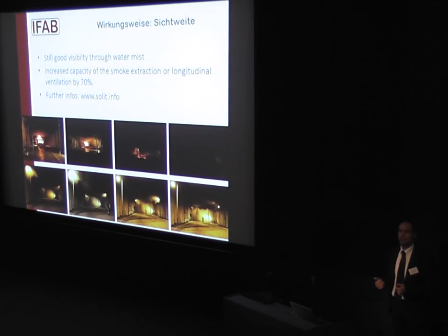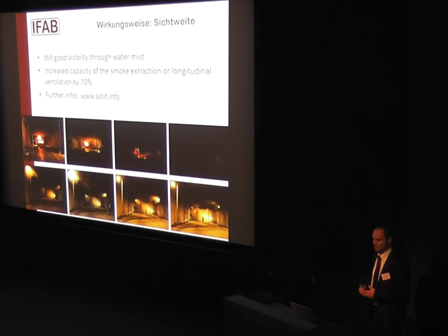What we found out is that we can increase the smoke extraction or the longitudinal ventilation capacity or efficiency by 70%. That's really an enormous number. So we can use a ventilation system which is designed for 30 megawatt together with a water mist system, and then you can control or keep the tunnel smoke-free for fires of around 100 megawatts. Similar thing with the infrastructure.